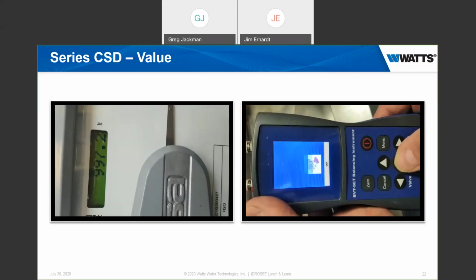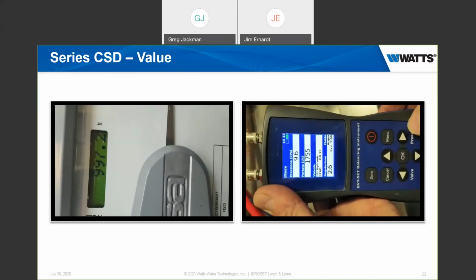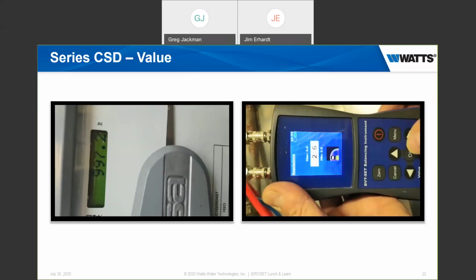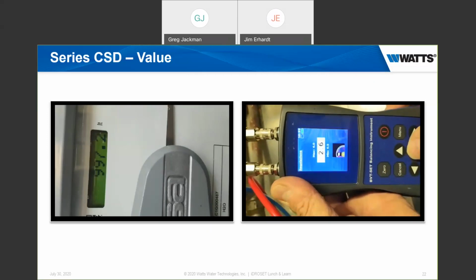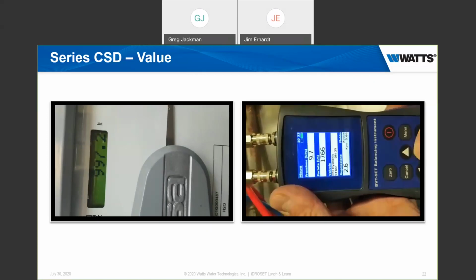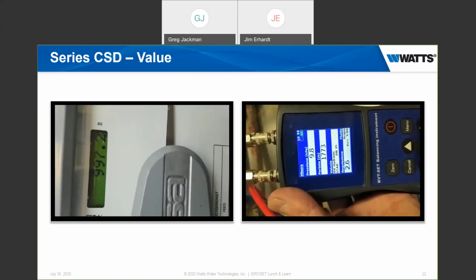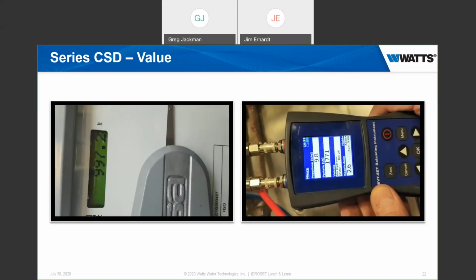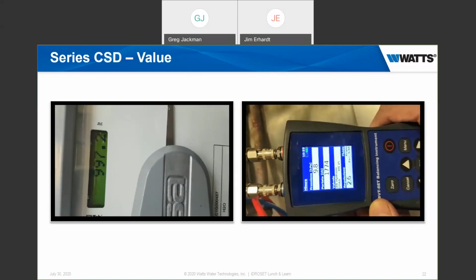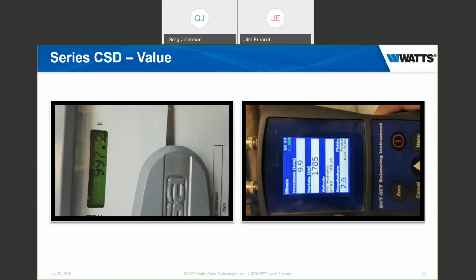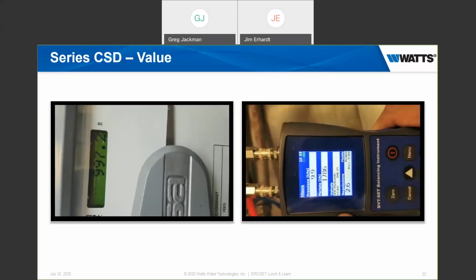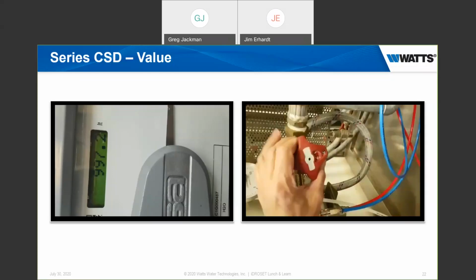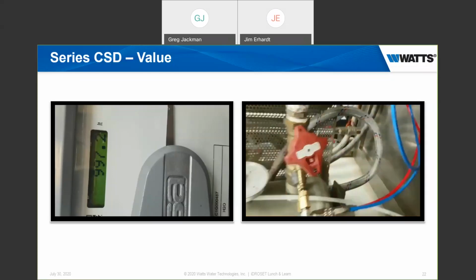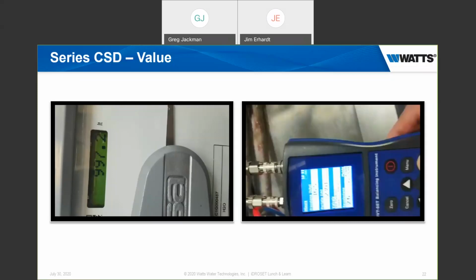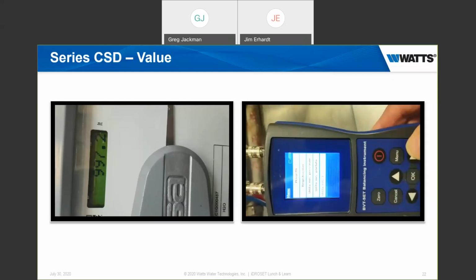And every time you adjust the flow, he has to go in and take a reading on his instrument. So he's doing this over and over, and every time he turns the valve, he actually has to take another reading and see where the flow is. And when he finally gets it to the point where it needs to be, he can finally say, okay, good, that valve is now set. Now, don't forget that when we adjust other valves in the system, the flow on this one's going to change. So he has to come back. He's not doing this just once. Might be doing it 2 times, 3 times. You might be doing as many as 5 times, depending on the complexity of the system.